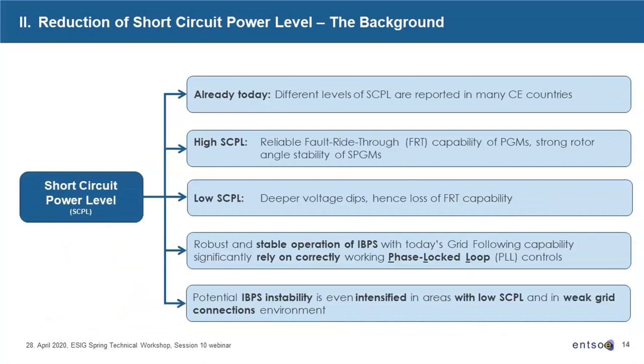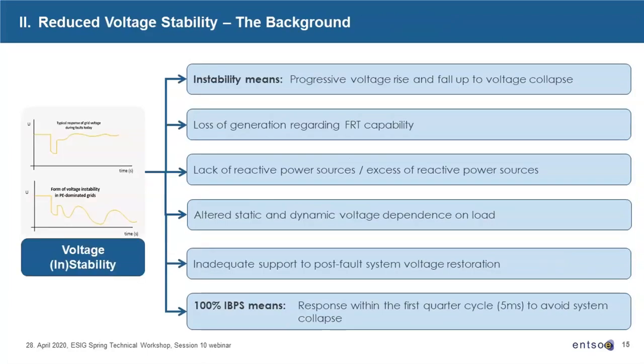Short circuit power level: some details here about this. I won't go through the details now due to the limited time, but the slides will be circulated afterwards, so everybody can read them and contact me if further questions arise on these matters. Same for voltage stability issues: also a number of aspects and observations related to this, for example, reduced fault ride-through capabilities. In future we would experience a much faster response being needed, due to the dynamics of inverter-based power sources, to avoid voltage and system collapses.